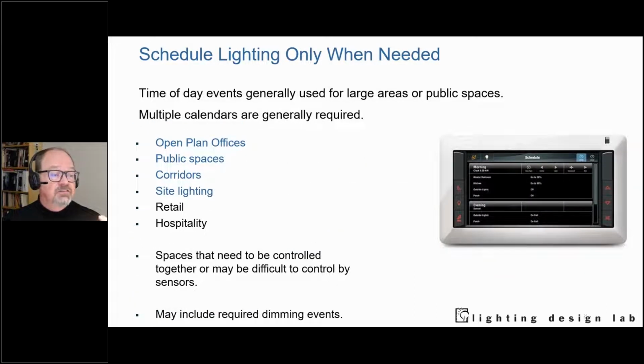Schedule—scheduling events for when the lights need to be on or off. Time of day scheduling is not nearly as important as it used to be, thanks to the ubiquity now of sensors. But I did mention the one place I really use scheduling is telling the occupancy sensors: you're an occupancy sensor during these hours, you're a vacancy sensor during these hours. There are still lots of places where we use time of day schedules to turn lights on or off, or dim them, like parking lots.